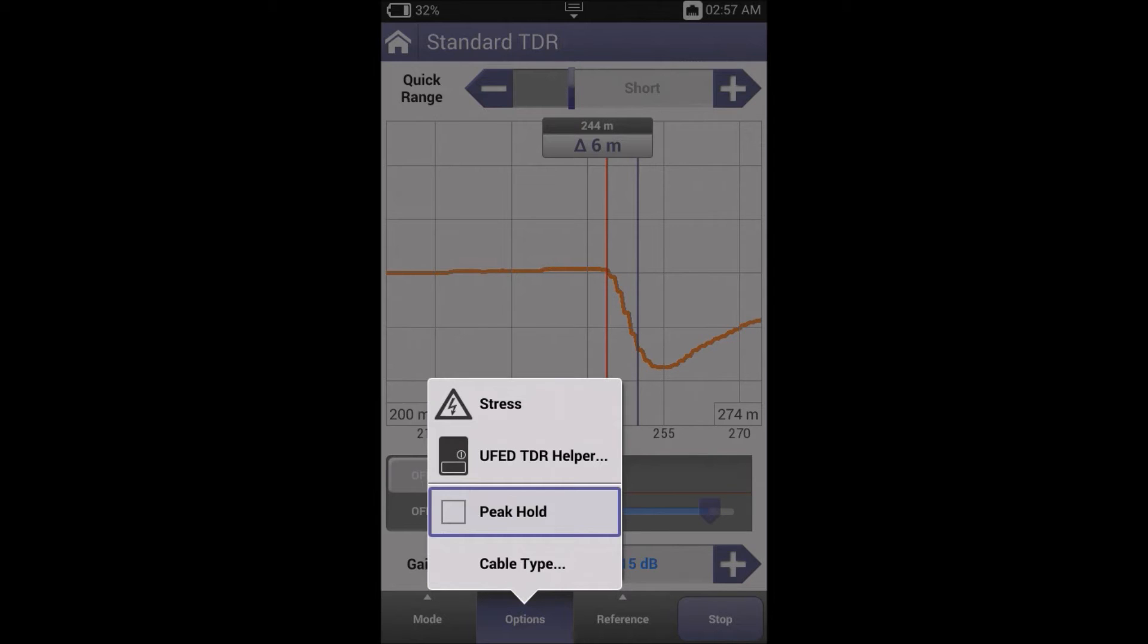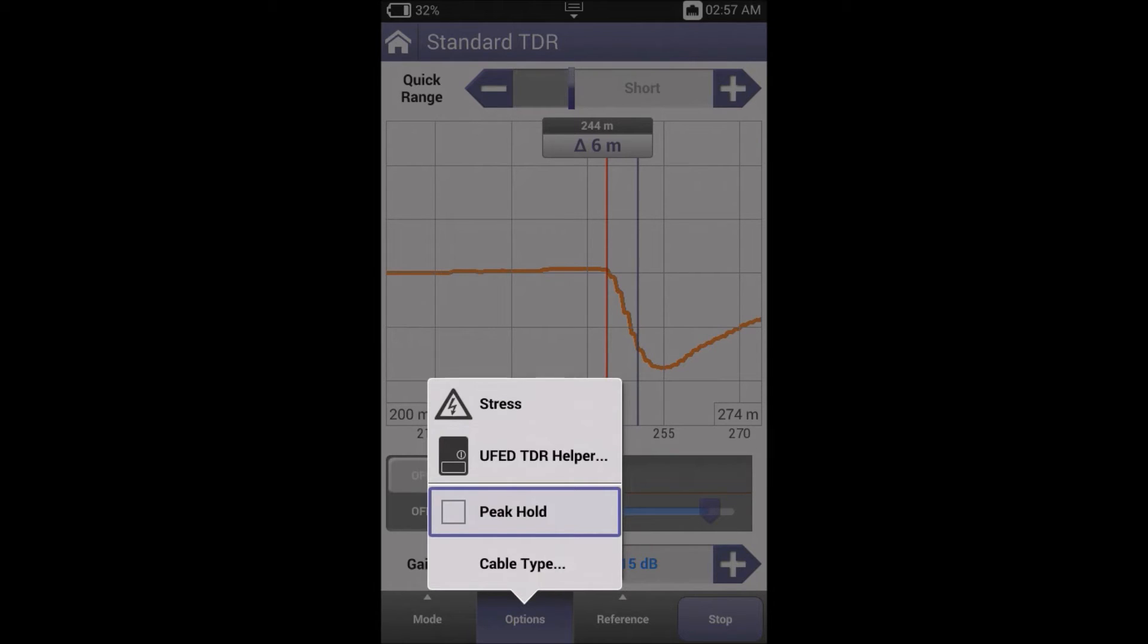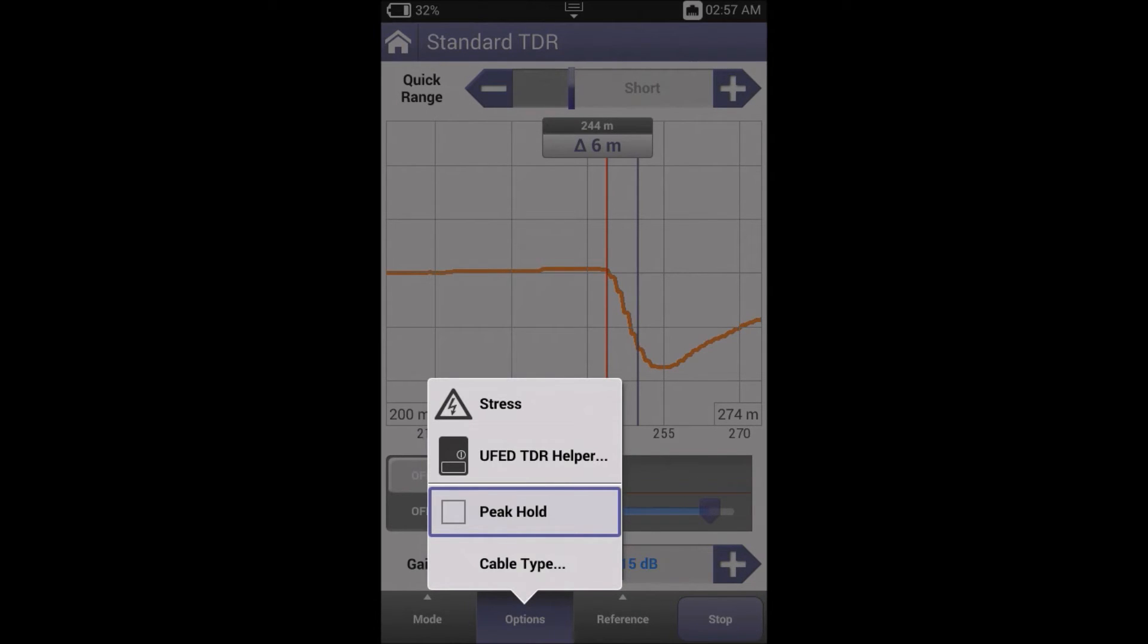By selecting options, we can see that stress and peak hold are highlighted. With peak hold, TDRs appear to run continuously. In reality, their operation is a series of snapshots, sending the high frequency TDR signal, waiting for the return reflection, and finally displaying the trace or reflection results.